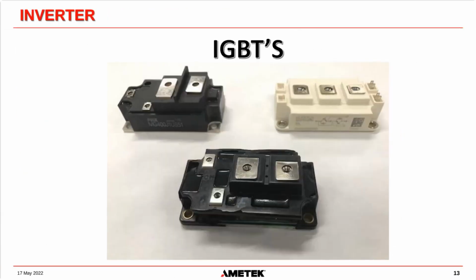And this is what IGBTs kind of look like, especially the ones inside of our inverter. They're high powered, so obviously they can usually handle 100, 200 amps, maybe even more. On this one here, this is probably the collector and the emitter, or it could be the other way around. And then we have our gate signals here. In truth, that's probably the emitter and that's the collector, because this is also the emitter, and you send a signal between the gate and the emitter terminals here, and it will allow power to flow through those two terminals. That's the same with this one down here.